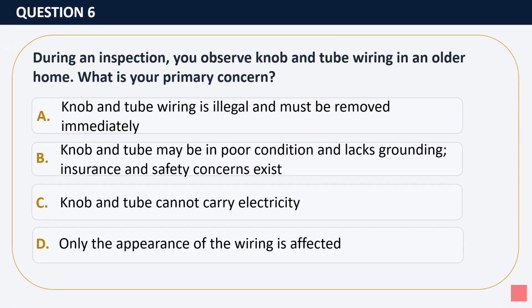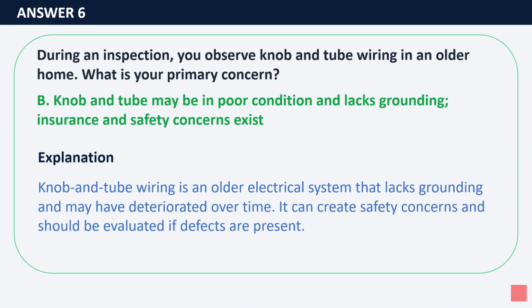Question 6. During an inspection, you observe knob and tube wiring in an older home. What is your primary concern? A. Knob and tube wiring is illegal and must be removed immediately. B. Knob and tube may be in poor condition and lacks grounding. Insurance and safety concerns exist. C. Knob and tube cannot carry electricity. D. Only the appearance of the wiring is affected. Answer B. Explanation: knob and tube wiring is an older electrical system that lacks grounding and may have deteriorated over time. It can create safety concerns and should be evaluated if defects are present.